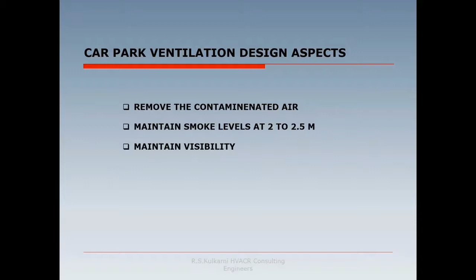With that, the flue gases are thrown out. That is the main criteria, or major motto, for the designers. And the second criteria is when we design the parking ventilation scheme, we should maintain the smoke levels below the 2.5 meter height. The reason is that 2 to 2.5 meters is the normal human being's height, so we can see the visibility is higher in this case. Also, the firefighters can reach the smoke or fire locations easily, which of course have good visibility.